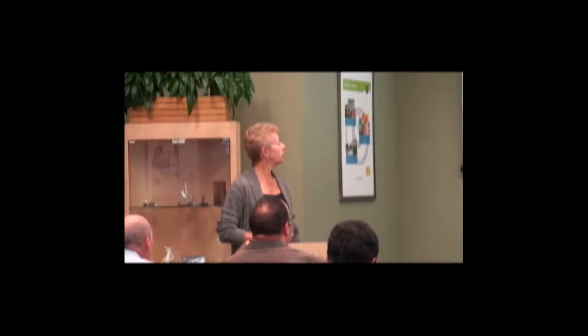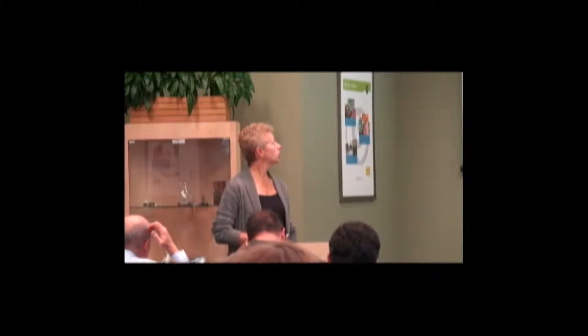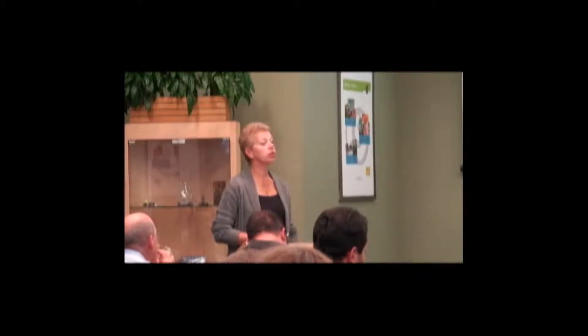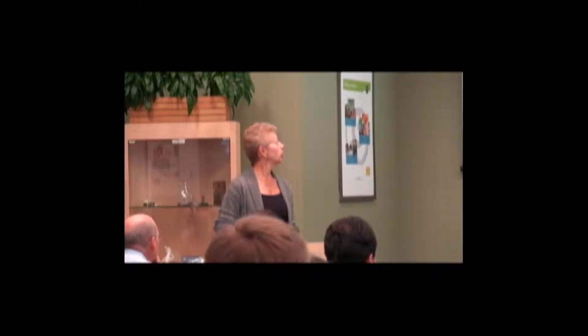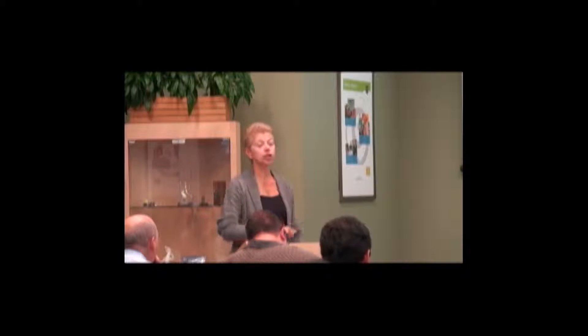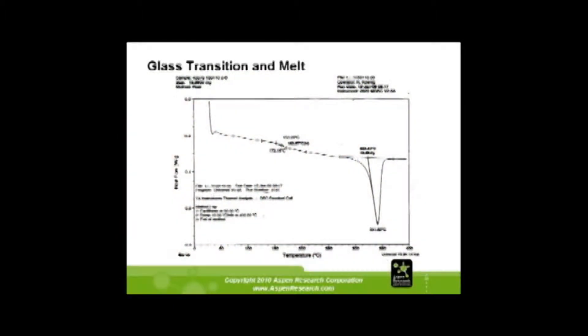By calculating with different methods, you can have as much as 45 degrees of temperature difference. So you really need to know which method you're using, especially if you're comparing results to someone else's data. Usually when you look at common reference data, the method isn't stated — so you've got to know what you're doing. Here is the melt: the heat of fusion for this sample is 42.39 joules per gram, which is the area underneath the curve.